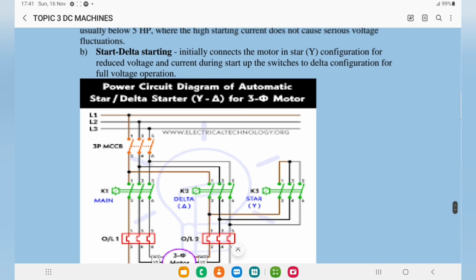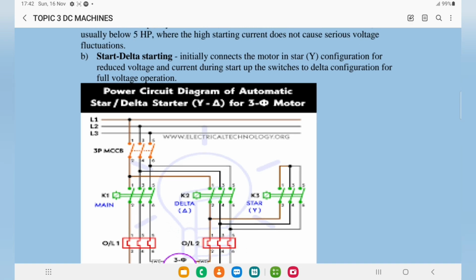The star delta means that the motor is connected in two ways. Initially the motor is connected in star for reduced voltage and current while it is starting. But in order to maintain full voltage and continued rotation, the motor will then switch to delta. So it is a connection of two sets: the star for starting, and the delta for maintaining the operation or rotation.